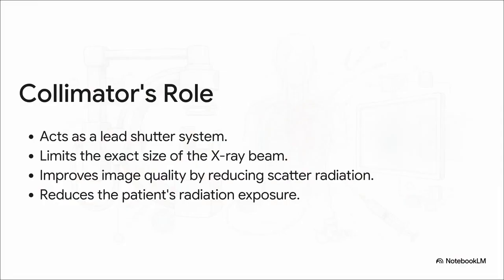But pulsed beams aren't the only safety feature we have. Enter our unsung hardware hero, the collimator. You can think of it as a highly precise lead shutter system attached right to the X-ray tube. It physically limits the exact size and shape of the X-ray beam before it even has a chance to reach the patient. And by strictly confining that beam, it accomplishes two totally vital things. First, it improves the image quality by cutting down on scatter radiation, and second, it directly prevents unnecessary radiation from hitting other parts of the patient's body. Oh, and it protects the doctors standing nearby too.